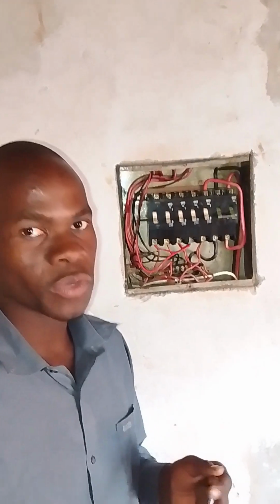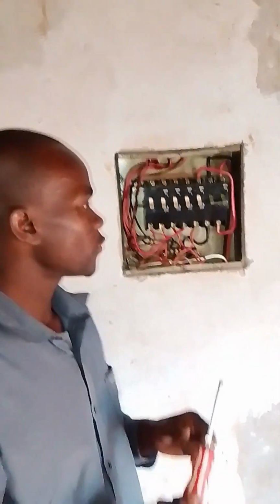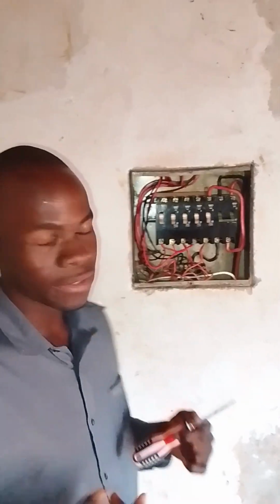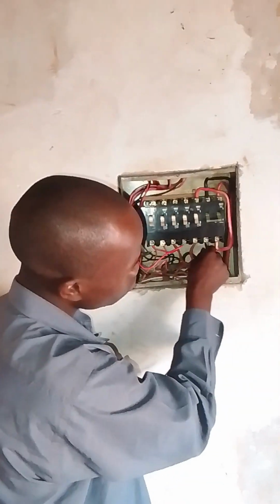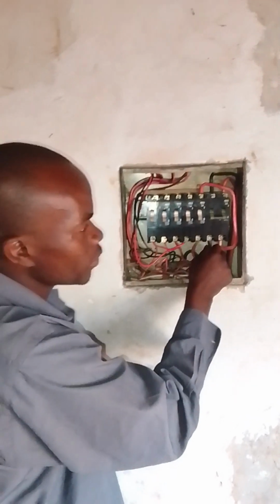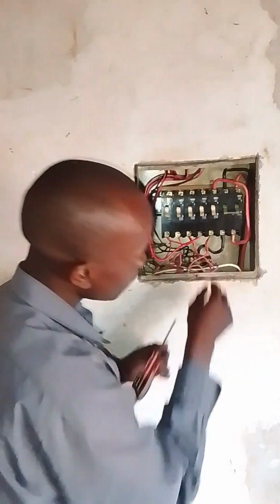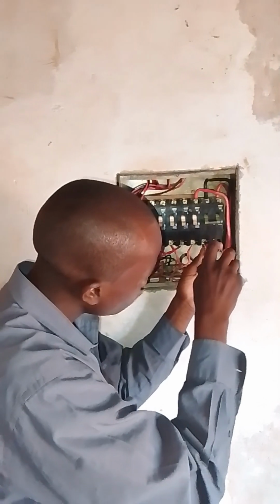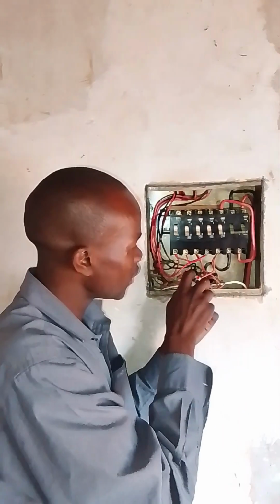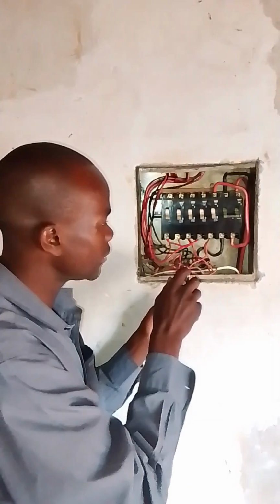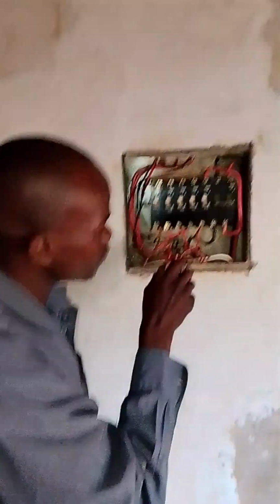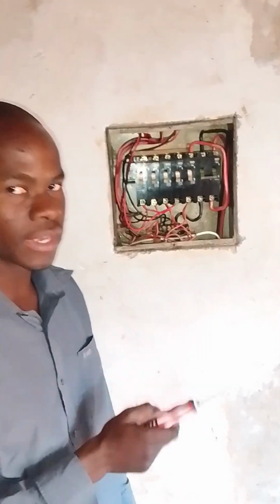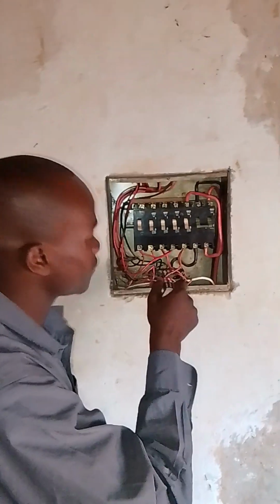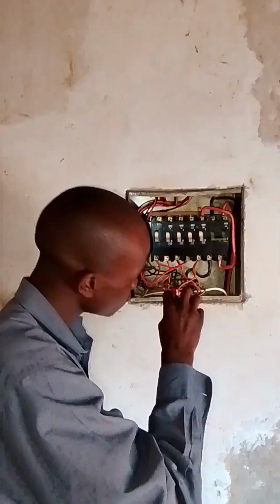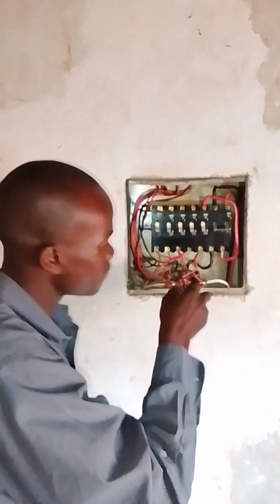like this. And then after this, you have to understand that we want the neutral bar. So what we do is we get the 10 millimeter cable again and connect it at the bottom of our double pole circuit breaker like this. And then we connect it to the common neutral bar right here. And take note that this common neutral bar is where all the neutral cables are placed, right? And then you'll be screwing these screws after you've placed the cable.